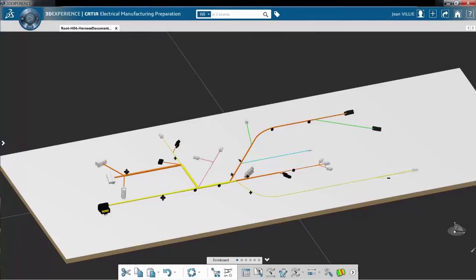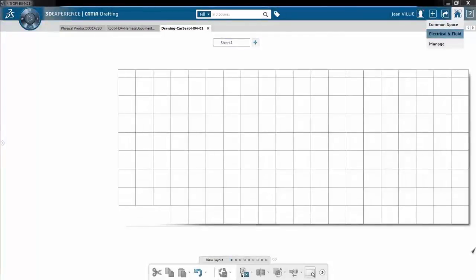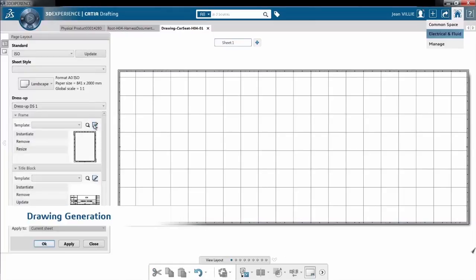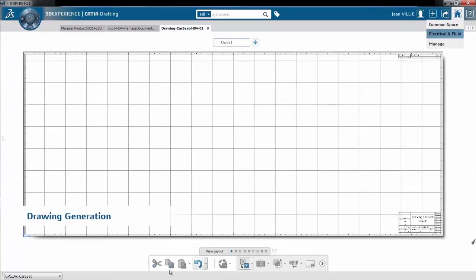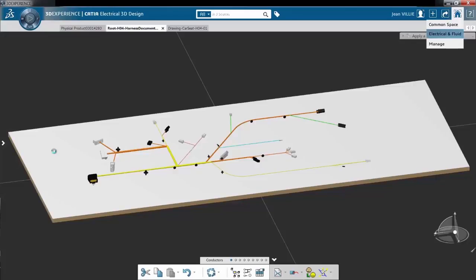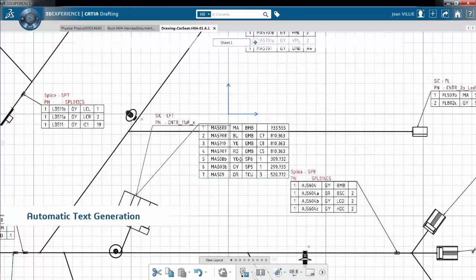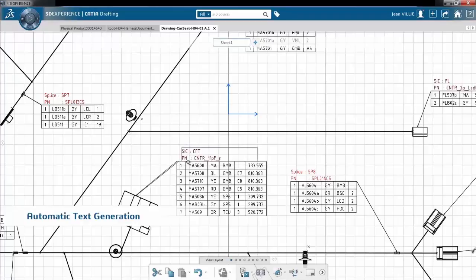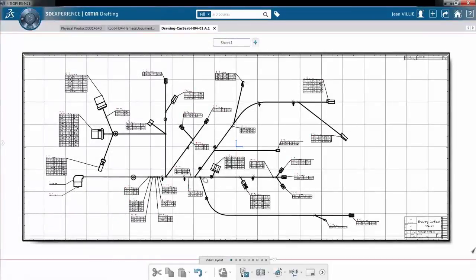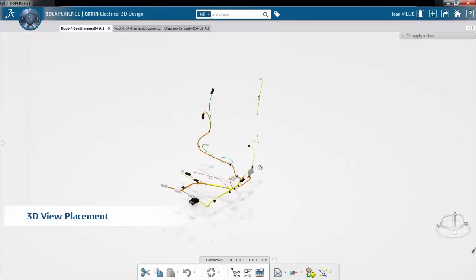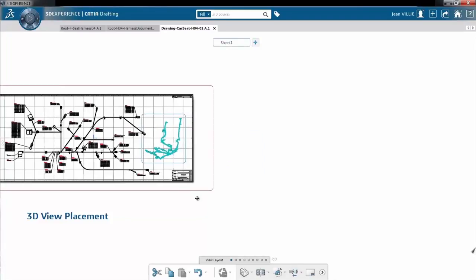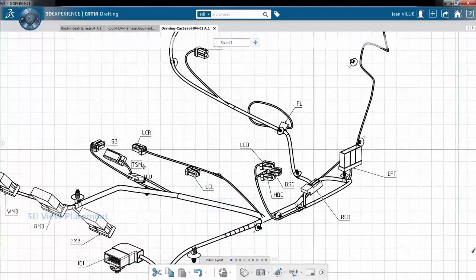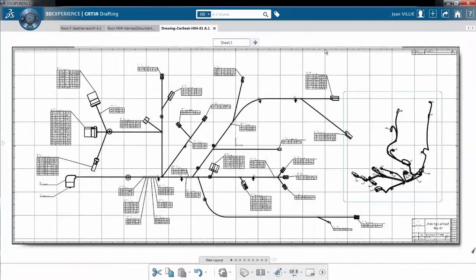When this is done, we have the harness in 3D on a 2D plane. We can now simply by using the drafting capabilities create the formboard documentation. We select the layout of the paper, we have a title block, and we start generating using some advanced automation scripts — automatic text generation. We create the full harness on the drawing. Since we also have the 3D view, it's easy to have an isometric view. By selecting a plane, we can create a small drawing on top of the formboard which enables manufacturing to have a 3D view and see the location of all the connectors in space.